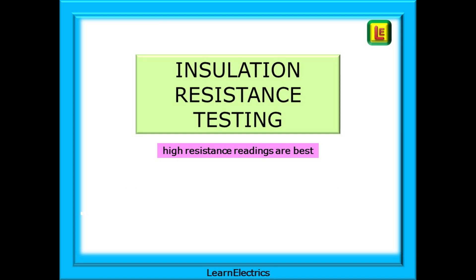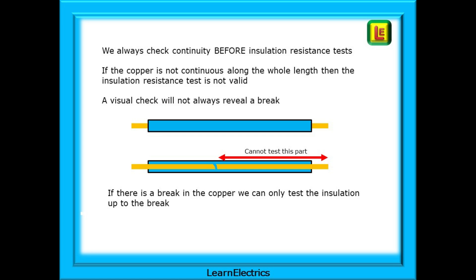Looking at insulation resistance testing now, keep in mind that high resistances are best for these tests - millions of ohms is what we want. We should always check continuity before the insulation resistance tests. If the copper is not continuous along the whole length then the insulation resistance test is not a valid test. Quite often a visual check will not reveal a break in the plastic insulation, and if there is a break in the copper we could only test the insulation up to the break, which is not good enough.